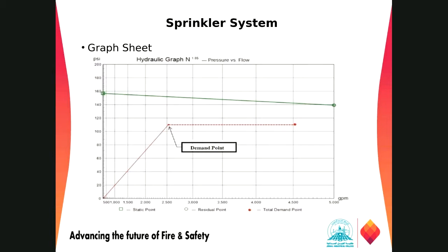So we have to add the fixed fire protection system demand plus the manual fire protection demand, right? Which is required by the various codes or the local jurisdiction. Like for the SABIC, what I have seen from the SCIS, they have given around 7,800 LPM for the fixed fire design, which will be coming from 3 hydrants to fight the fire.